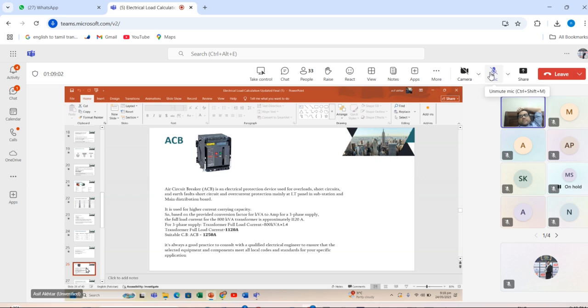So what is ACB? Can anyone tell me the meaning of ACB and where we will use it? Air circuit breaker. And what is MCCB? Miniature molded case circuit breaker, I think. No, miniature is MCB, miniature circuit breaker, and MCCB is molded case circuit breaker. An air circuit breaker is an electrical protection device used for overloads, short circuits, earth fault and overcurrent protection. It is mostly used in LT panels, in substations and main distribution boards.